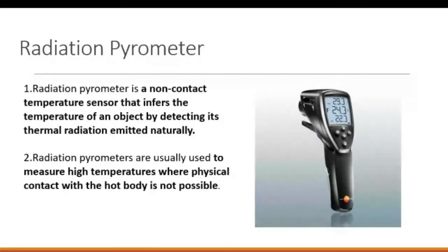A radiation pyrometer is a non-contact temperature device. It infers the temperature of an object by detecting its thermal radiation, emitted naturally. So when we direct the radiation pyrometer at a hot body, it captures the radiation and displays the temperature of the hot body. Radiation pyrometers are usually used to measure the highest temperatures where physical contact with the hot body is not possible. Next slide.